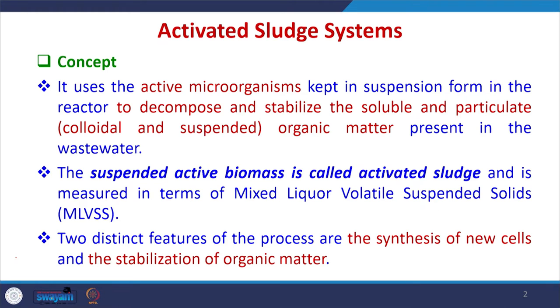This process is always used after primary treatment, where physicochemical treatment is done. After primary treatment, we try to remove the organic content mostly in the secondary treatment. The activated sludge process is the most common process used for removal of most organics present in the wastewater after removal of suspended and dissolved solids in the primary treatment. Activated sludge systems use active microorganisms kept in suspension in the reactor to decompose and stabilize the soluble and particulate organic matter present in the wastewater.